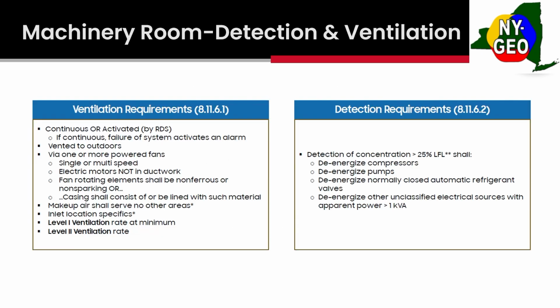So we'll get into machinery rooms. Machinery rooms are a big deal with the A2Ls, whether it's a heat pump or a chiller. This is just the ventilation requirements. There's a whole other set of building requirements when you're doing a machine room. And when I say machine room, don't confuse it with a mechanical closet where someone has an air handler, or where we talk about refrigerant pipe running through. This is a separate room from the building, no penetrations into the main corridor, all the duct penetrations sealed. So keep that in mind. Think of a chiller or a boiler inside of it, not a typical mechanical closet.